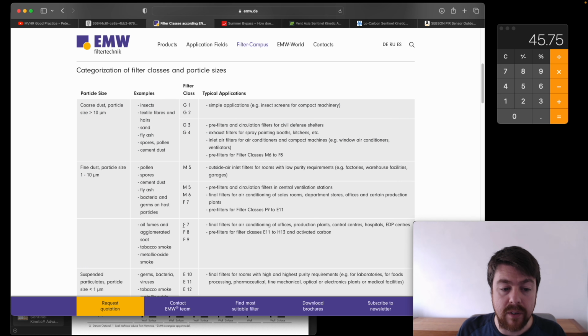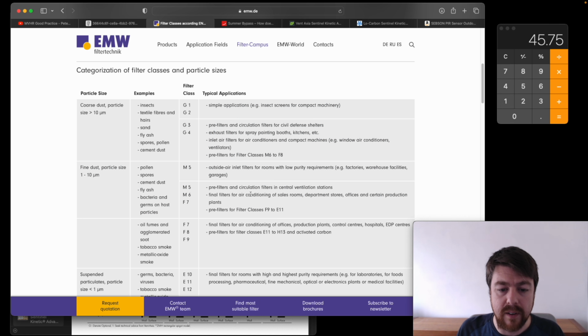Sure enough, there is one. Typical units are down around these filter classes - you can see the particle sizes and typical applications: final filters for air conditioning, sales rooms, department stores, offices. Then you can get up to the F7 grade, for more dust sensitive areas. I did find a heat recovery unit that could take these much finer F7 filters.